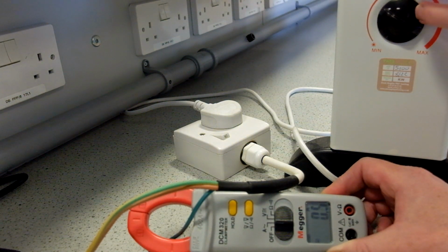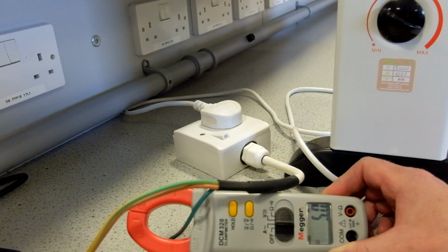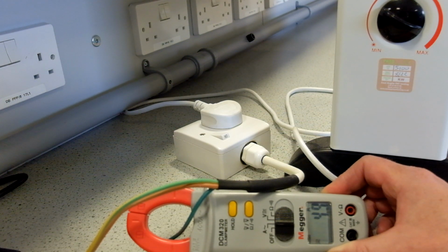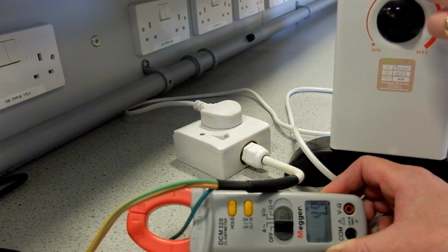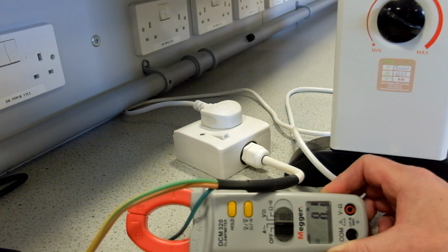If we switch 1250 on, the prediction was 5.4. We're measuring 4.9 amps coming out, a little bit lower than I expect. That may be because the voltage is a bit lower than 230. And if we do 2000 watts, we expect 8.7, and what we're measuring is 8.1 amp. So all three readings are consistently a little bit below what we would expect or predicted from 230 volts.